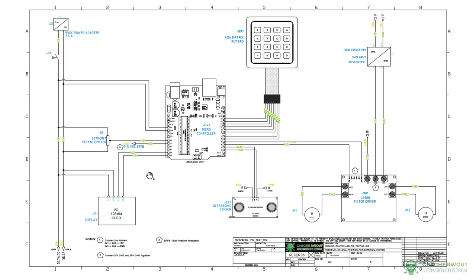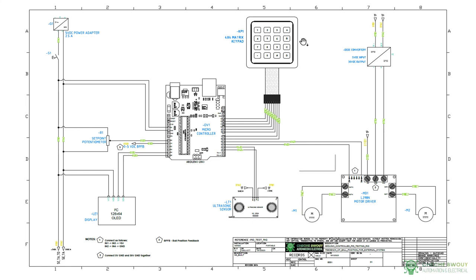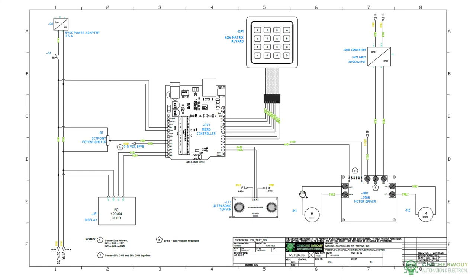Another thing to note about reading the schematic is wire numbers. So on here we have it formatted as the sheet number, which is sheet 01. So 01 comes first, and 6E is actually the location on the schematic diagram. That is in 6, that is in E, and it's the first wire that started in 6E.